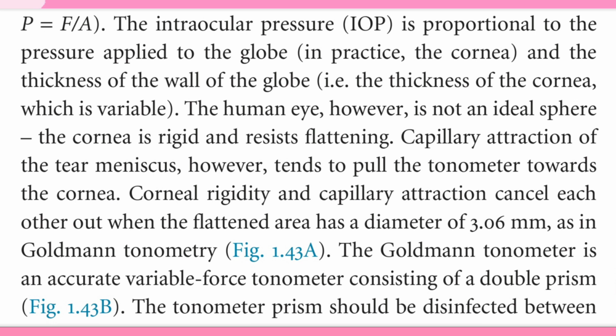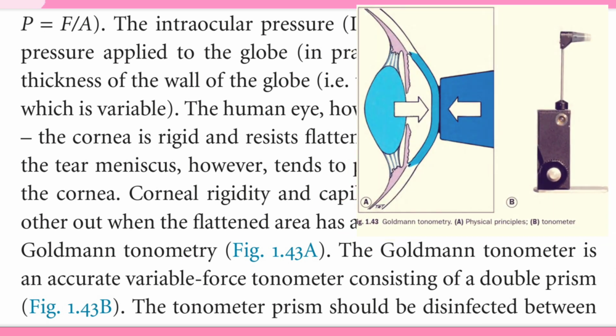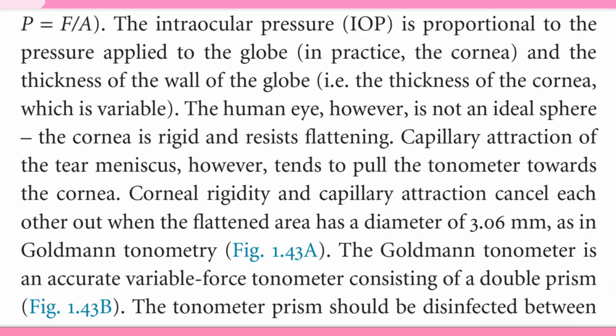The human eye, however, is not an ideal sphere. The cornea is rigid and resists flattening. Capillary attraction of the tear meniscus, however, tends to pull the tonometer towards the cornea. Corneal rigidity and capillary attraction cancel each other out when the flattened area has a diameter of 3.06 mm, as in Goldmann tonometry (Fig. 1.43a). The Goldmann tonometer is an accurate variable force tonometer consisting of a double prism (Fig. 1.43b).